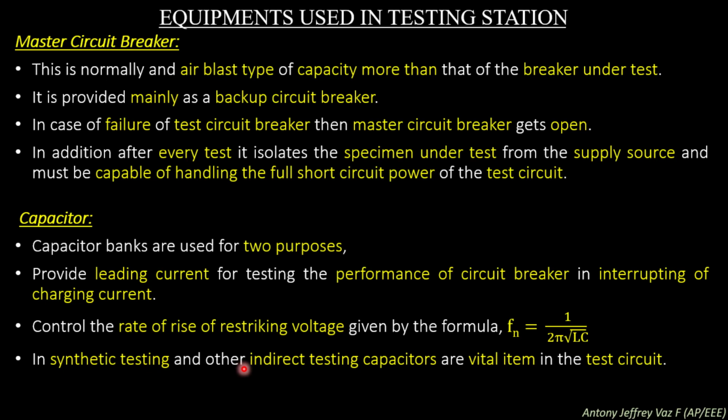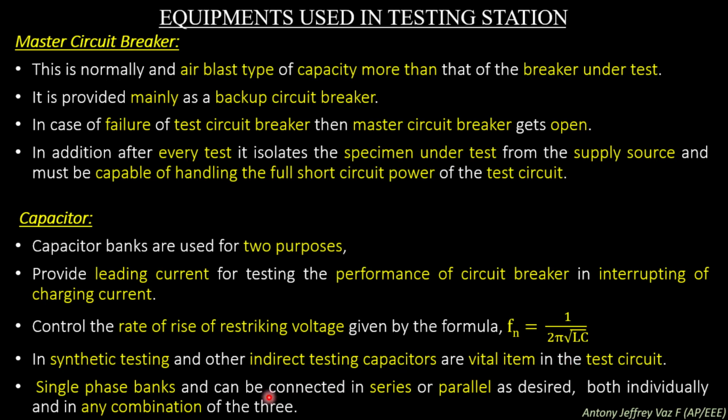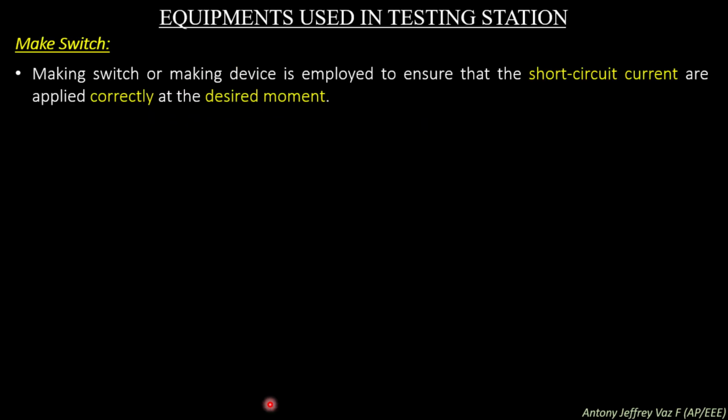In synthetic testing and other indirect testing, capacitors are a vital item in the test circuit. For doing synthetic testing and indirect testing of a circuit breaker, the capacitor is a vital item in the testing station. Single phase banks can be connected in series or parallel as desired, both individually and in any combination of the three. So, like the resistor and reactor, capacitors can also be connected in series and parallel combination, and the capacitance value can be increased or decreased as per the requirement.